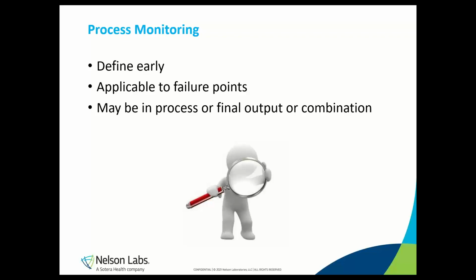You may want to consider either purchasing some equipment or investing in a correlation study to show that a test you can do each day relates to a more complex test that you perform with less frequency at an outside lab. The example with the graphs of peel strength versus visual characteristics would be an example of how a correlation study could be done to show the relationship of an easy test like visual inspection to a test that required specialized equipment like seal strength. If you do decide to implement internal testing, remember to factor in all the costs, including the initial cost of the equipment, the cost to qualify the equipment, to calibrate and maintain the equipment, to validate the test method, train employees, and maintain the expertise to keep the equipment operational.